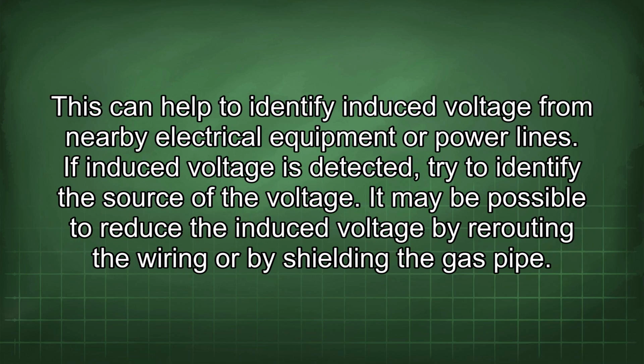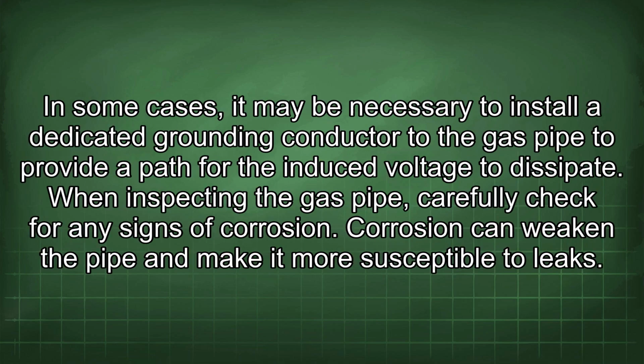This can help to identify induced voltage from nearby electrical equipment or power lines. If induced voltage is detected, try to identify the source of the voltage. It may be possible to reduce the induced voltage by rerouting the wiring or by shielding the gas pipe. In some cases, it may be necessary to install a dedicated grounding conductor to the gas pipe to provide a path for the induced voltage to dissipate.